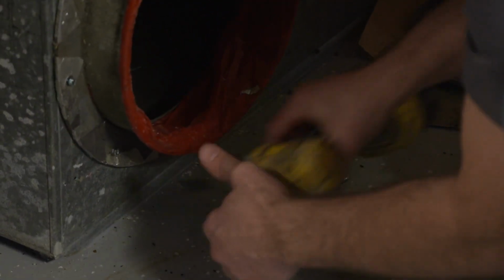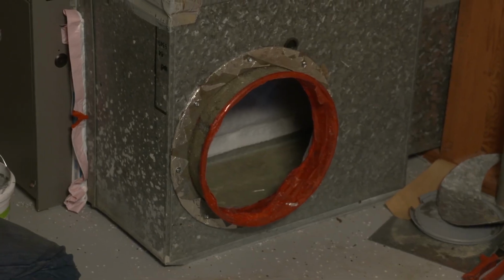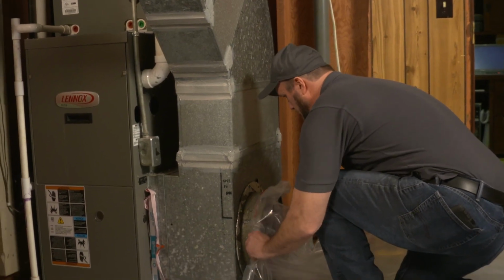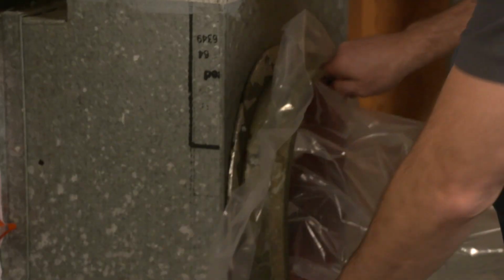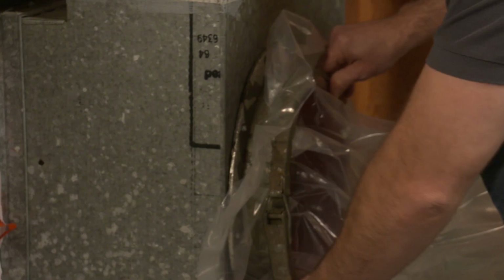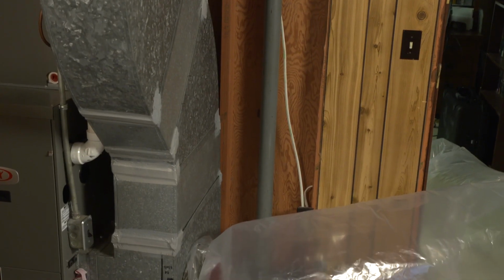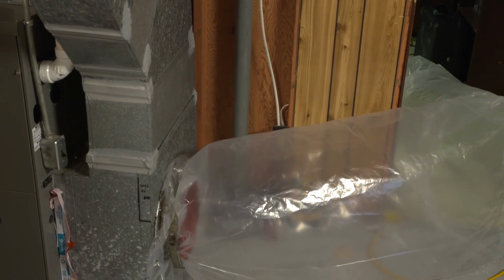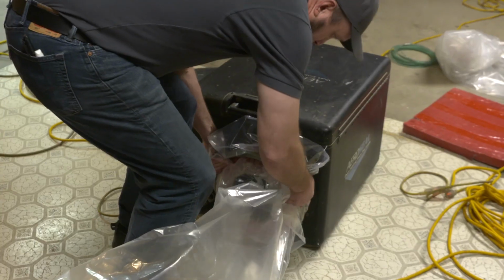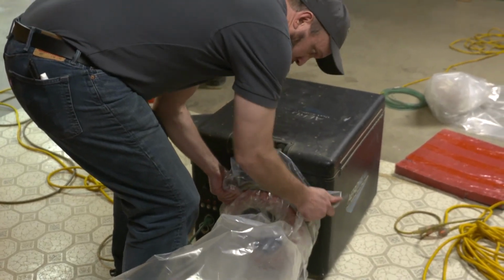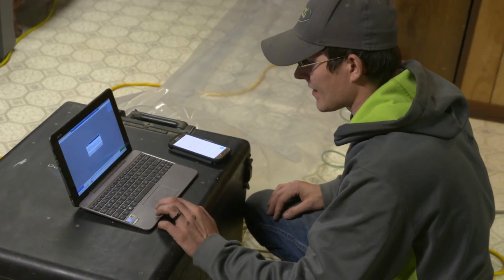Explain Aeroseal and how that works. Aeroseal is a process of taking a glue and heating it up, atomizing it, turning it into a mist that we then inject inside of the duct system. From there, it seeks out the leaks and seals them shut. Does it fill the entire duct system with a sticky glue? No, actually the glue is inside of there, but it's only going to come out where there are leaks.